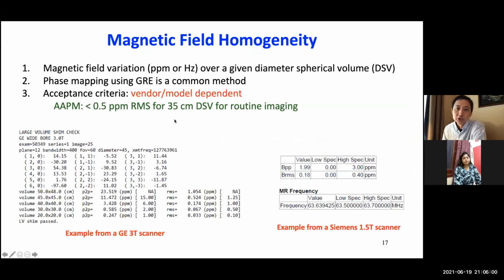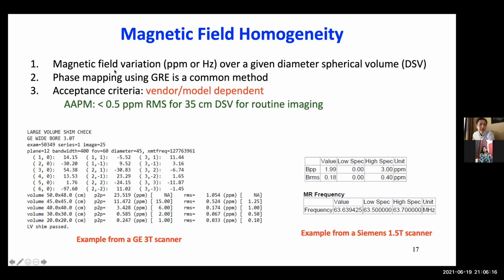The next is spatial homogeneity of the magnetic field. This is very important for image quality, and physicists are required to test it annually, every year. Just a brief introduction: the field variation is usually described by ppm or hertz over a given diameter spherical volume, or DSV. So basically we use a large homogeneous phantom, and we can look at the spatial homogeneity within a certain diameter of spherical volume. The standard method is to use the gradient echo sequence and do phase mapping. We look at the phase image. That's the standard method. And the acceptance criteria are vendor and model dependent.